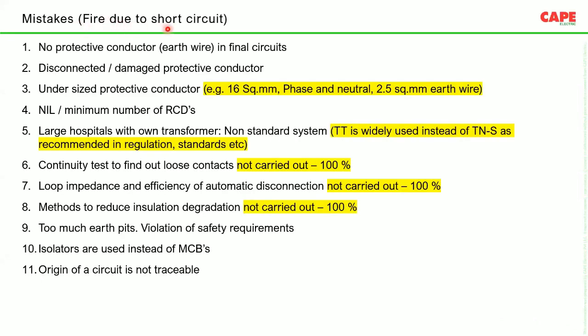Now, from the survey, the general findings we see are, in a lot of cases, there is no protective conductor, no earth wire in the final circuit. In the final circuit, in the sense, in the medical location, there are sockets available, but there is no earth wire on the socket. Most often these are disconnected or damaged protective conductors. Number 3 is an undersized protective conductor. That means the phase and neutral are 16 square mm, but the earth wire is only 2.5 square mm. This is actually a violation. Up to 16 square millimeters, phase, neutral, and earth must be the same size.